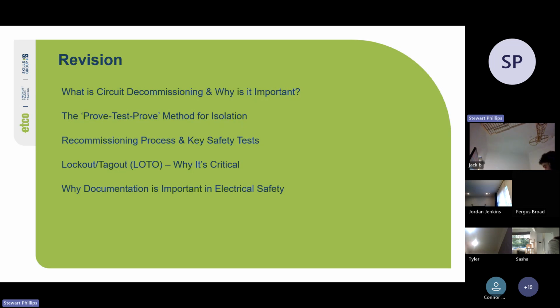When you lock out a source of energy, you put a multi-lock on it and everyone working on it adds a lock, plus the supervisor puts a lock on it too. That way the supervisor's lock is the last one to be removed, so the machine can't be turned on until he's talked to every single person and confirmed their job's done and everything's ready to go.